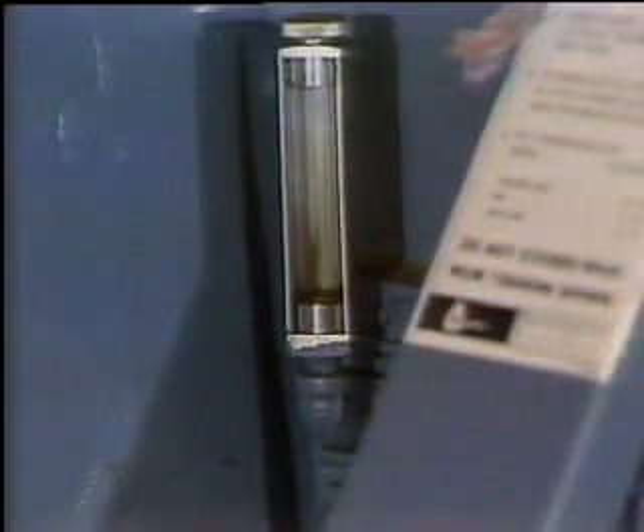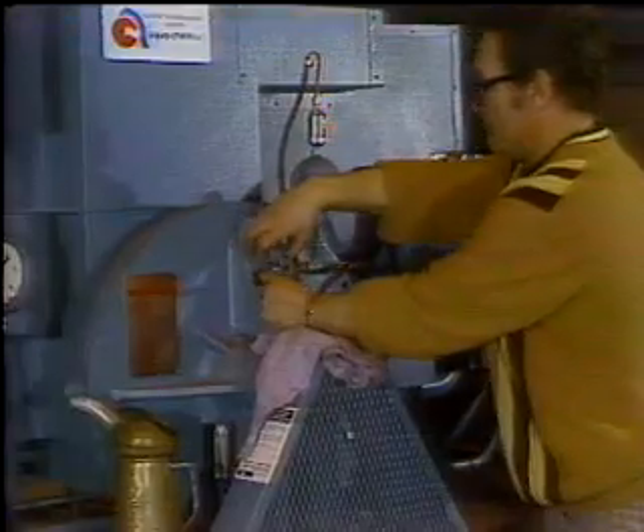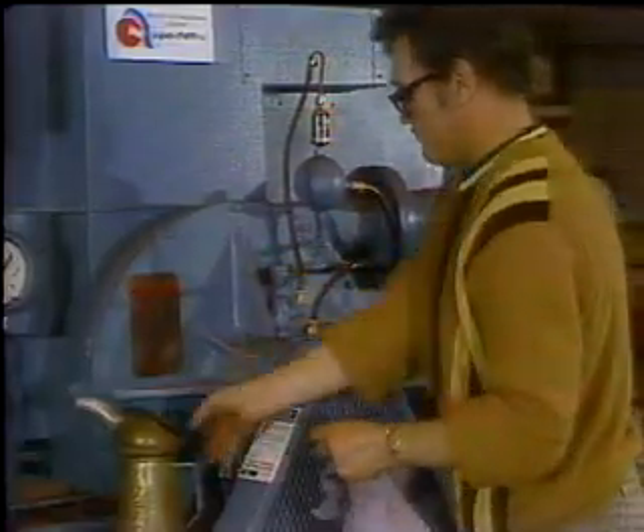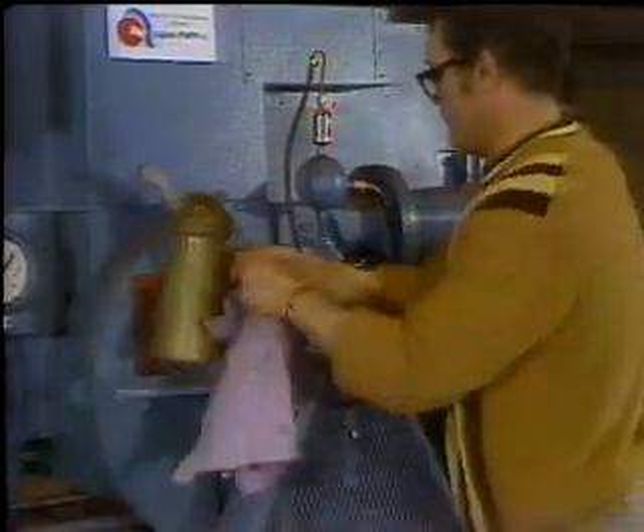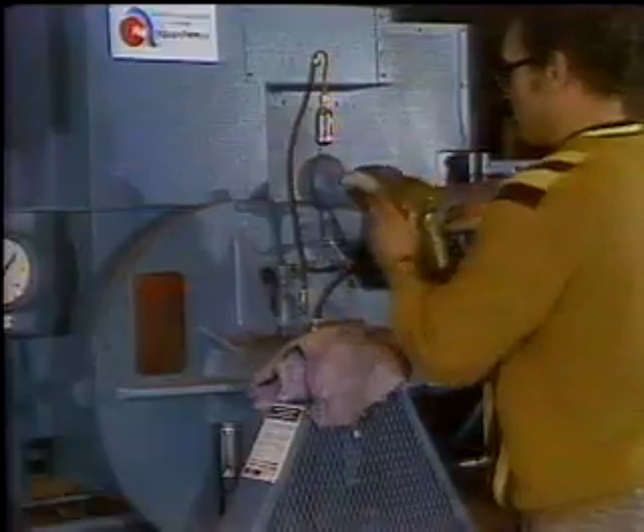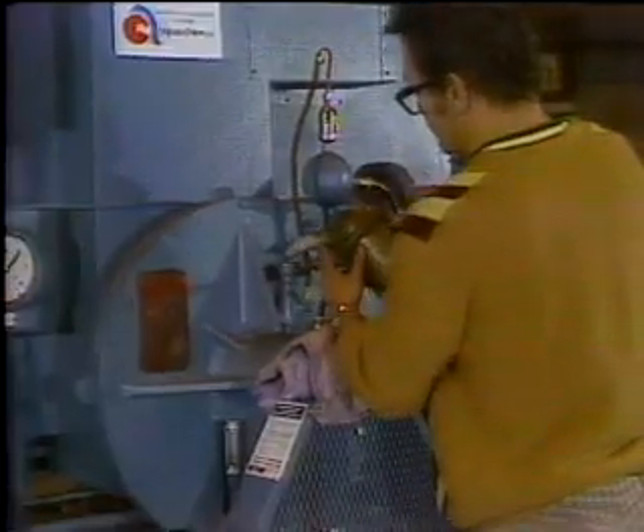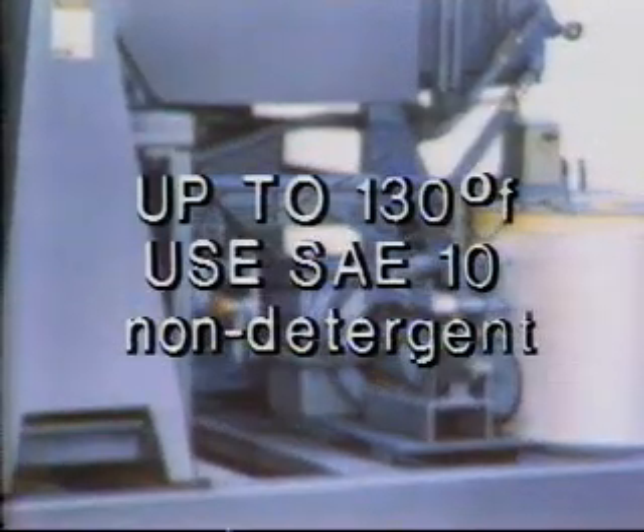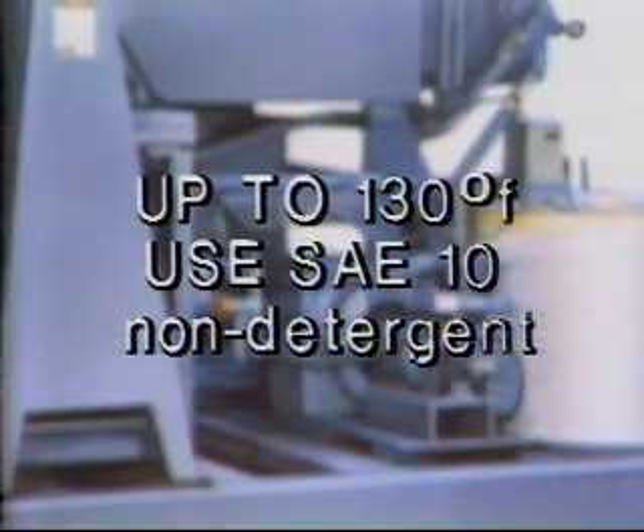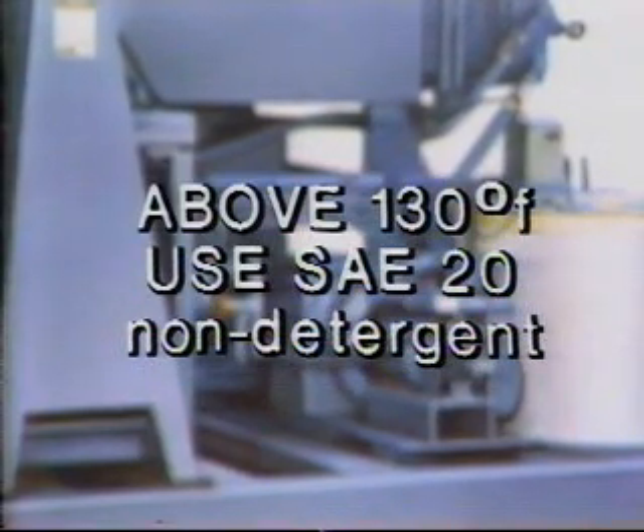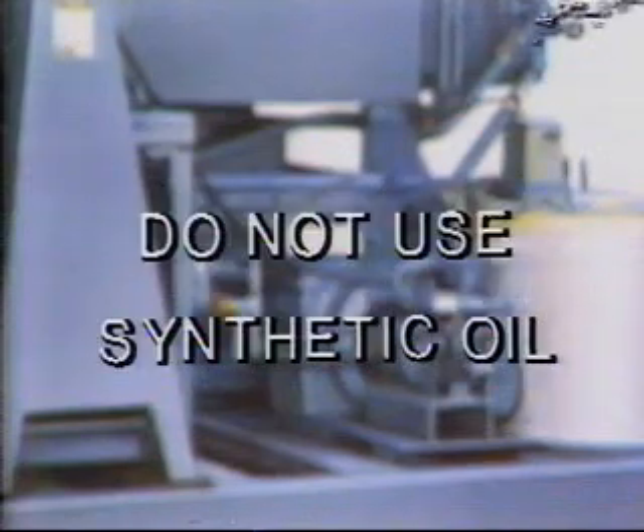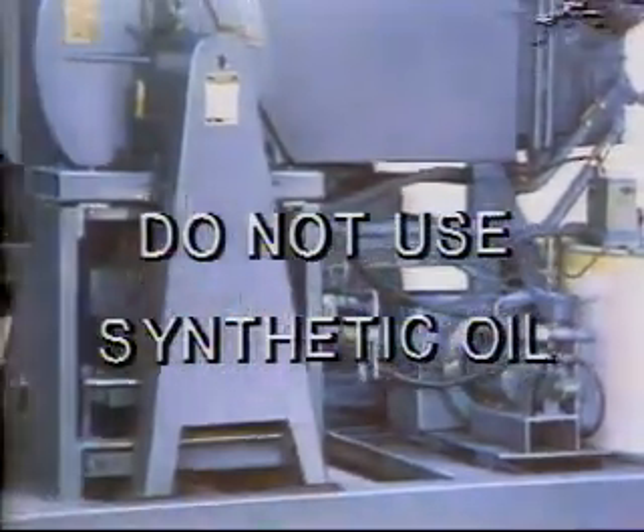Lube oil is measured here on this sight glass. It should be about a half an inch from the bottom. If it isn't, add the recommended 10 or 20 weight non-detergent oil. The viscosity of the oil depends on the normal oil operating temperature. For up to 130 degrees, use SAE 10. For above 130 degrees, use SAE 20. Now, don't use any of that expensive synthetic stuff. Regular oil is best for this particular system.